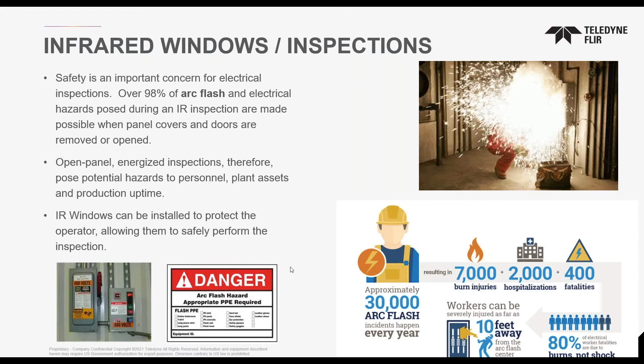It keeps that worker isolated from that live switchgear or panel, ultimately reducing the risk. Looking at the hierarchy of controls, PPE is the last thing we do. We always want to do it, but just because you have PPE on doesn't mean you're going to be safe. Sometimes our PPE fails, and sometimes it's not meant to protect you from an arc flash incident. So the more you can get away from that danger, the better.